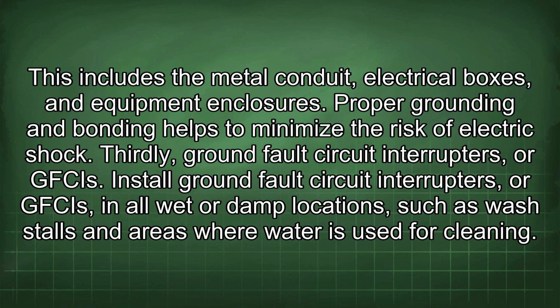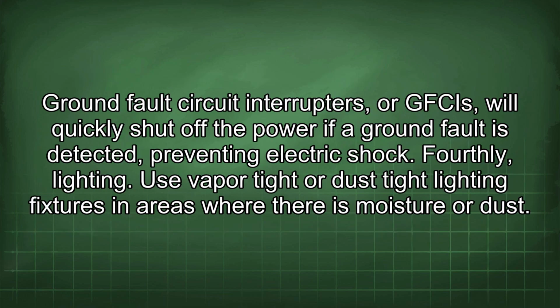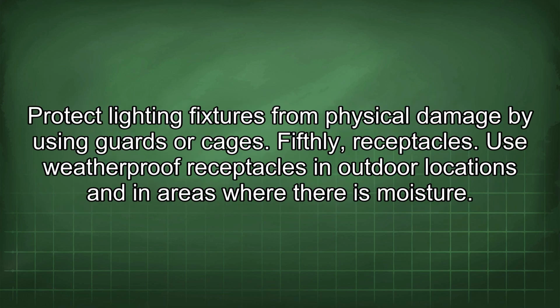Thirdly, ground fault circuit interrupters, or GFCIs. Install ground fault circuit interrupters, or GFCIs, in all wet or damp locations, such as wash stalls and areas where water is used for cleaning. GFCIs will quickly shut off the power if a ground fault is detected, preventing electric shock. Fourthly, lighting. Use vapor-tight or dust-tight lighting fixtures in areas where there is moisture or dust. Protect lighting fixtures from physical damage by using guards or cages.